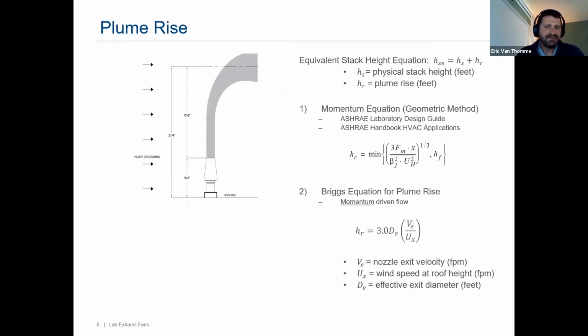Plume rise is a very common and typical resultant criteria that is produced by the fan manufacturers. If you have a physical stack, it's very easy to measure, and you know what your plume is, or what your physical stack height is going to be. But if you're going to use a virtual stack method for a laboratory exhaust fan system, it's a little bit more difficult to measure what that height is.